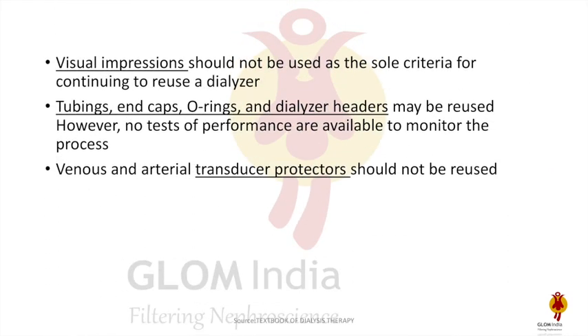Visual inspection is generally considered the sole criteria in many dialysis centers, but it should not be practiced as such. Tubing end caps, O-rings, and dialyzer headers can be reused. However, no tests of performance are available to monitor the process. Venous and arterial transducer protectors should not be reused.